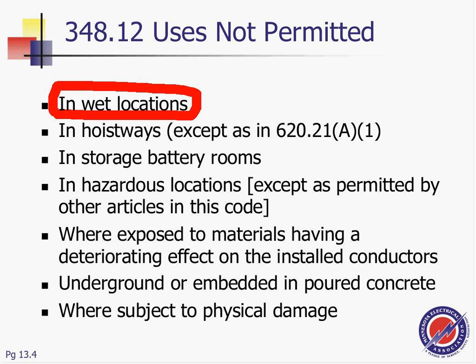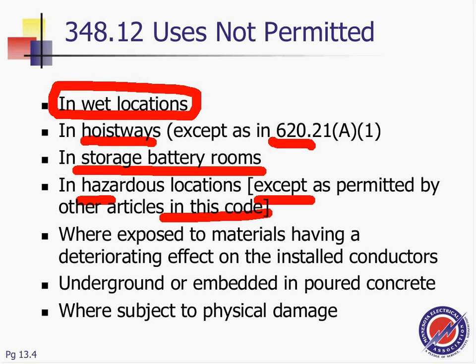It doesn't have to be outside. It could be any wet location. Hoistways for elevators, hoistways for environmental air, or any hoistways. They don't want you to. There are some exceptions, but for the most part, it's not allowed. In storage battery rooms, this is not your conduit of choice. Hazardous locations, with some exceptions, you can find a flex that you can use in a hazardous location, Class 1 Div 1 and 2 or Class 2 Div 1 and 2. It has to be rated for hazardous locations, because there are machines in hazardous locations that need flexibility. So there is a flex that you can use in a hazardous location. It has to be, of course, rated for that particular hazard.